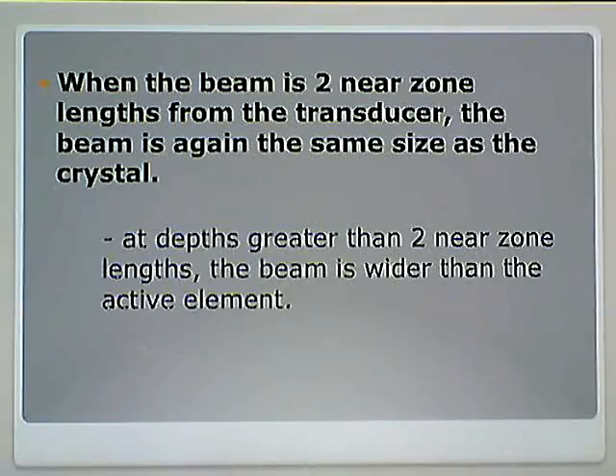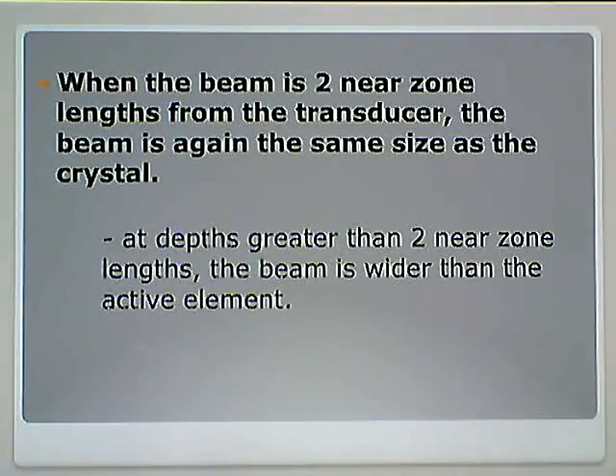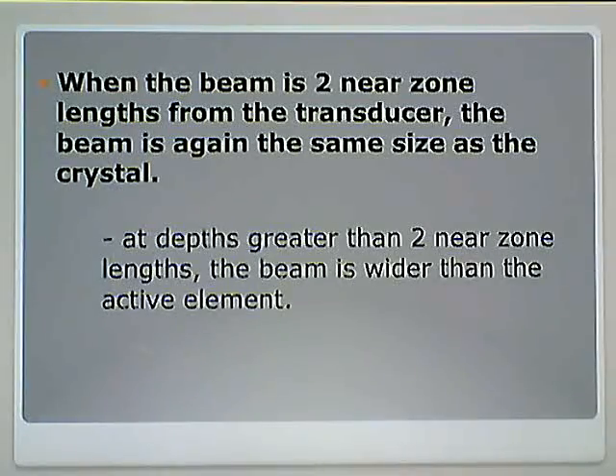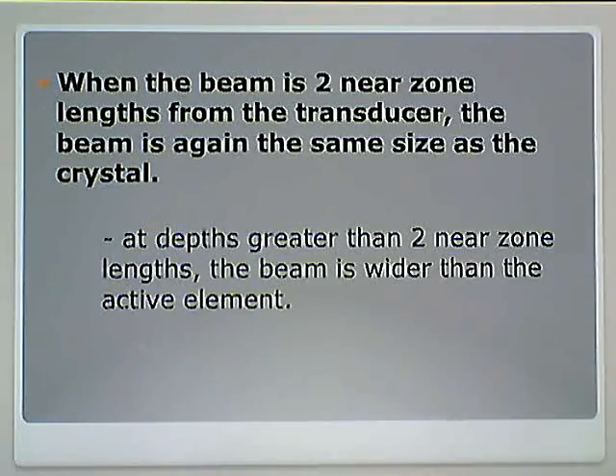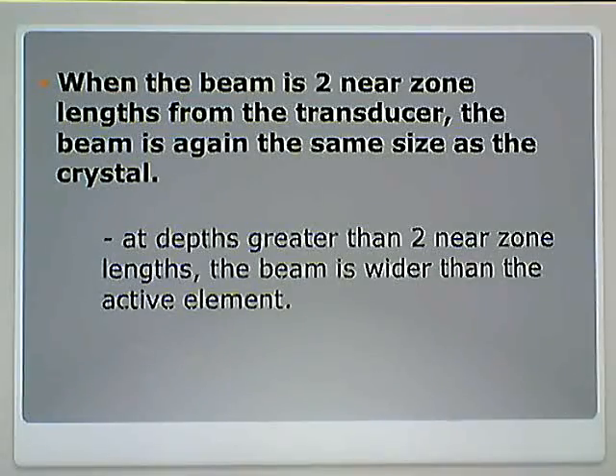Anything past those two near zone lengths — remember, in the far field, the beam diverges — so anything past that, the beam diameter is wider than the active element. It just goes on and on.